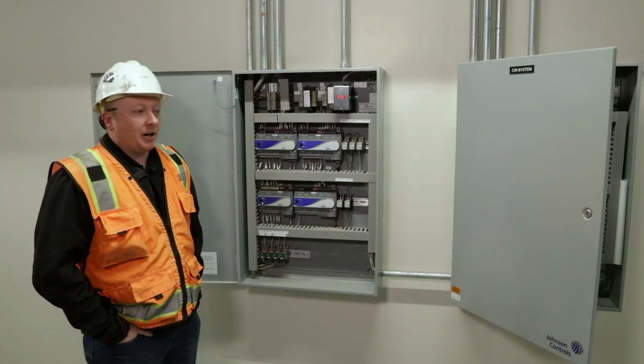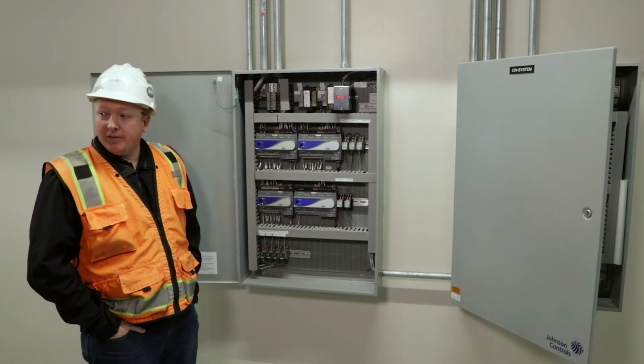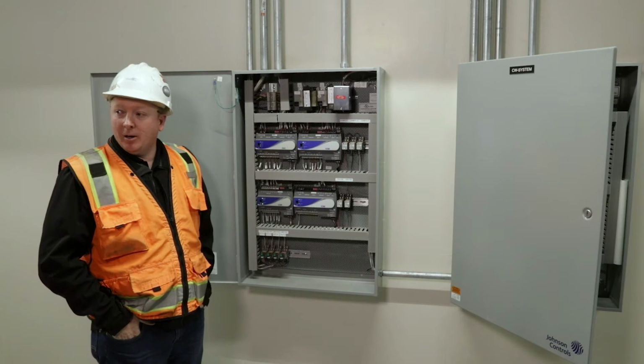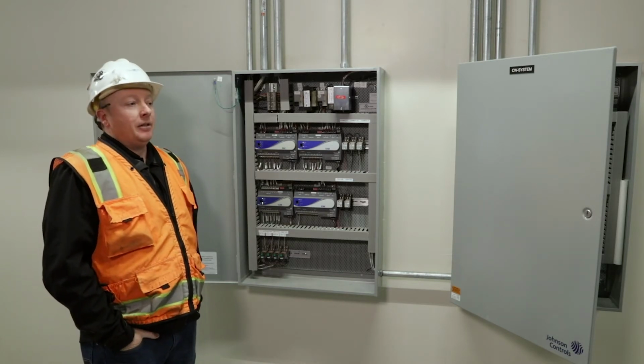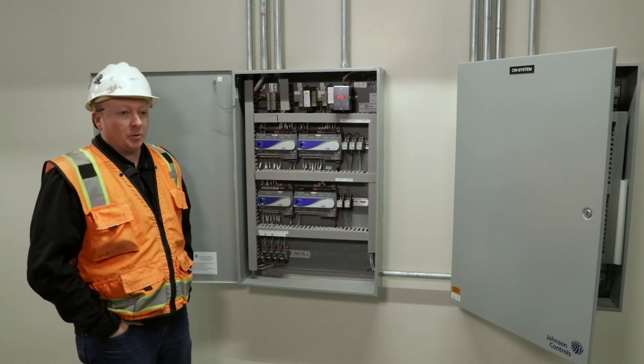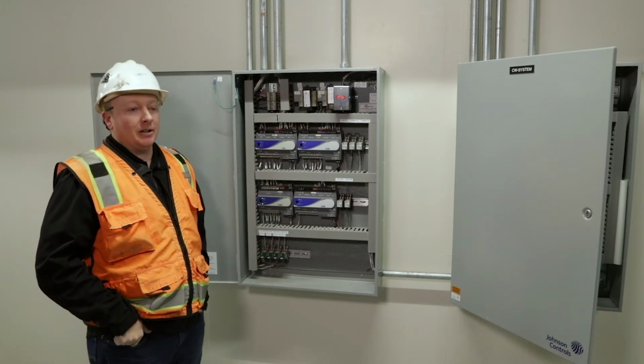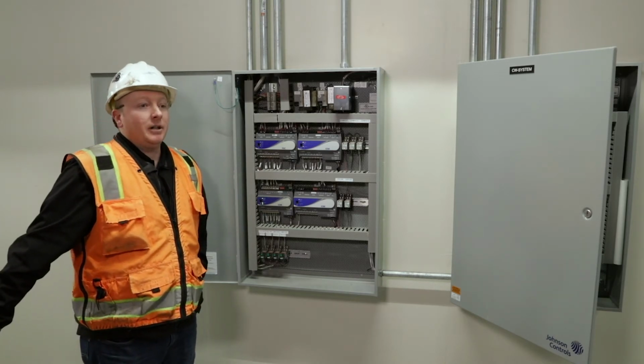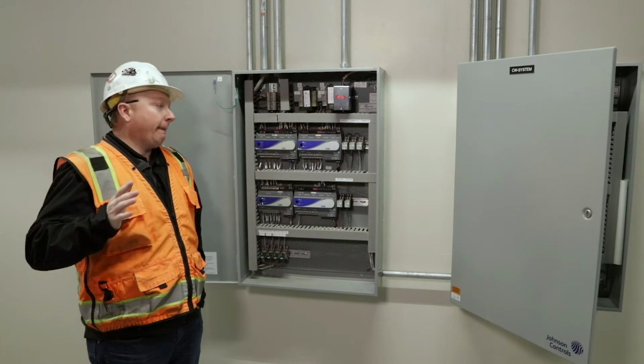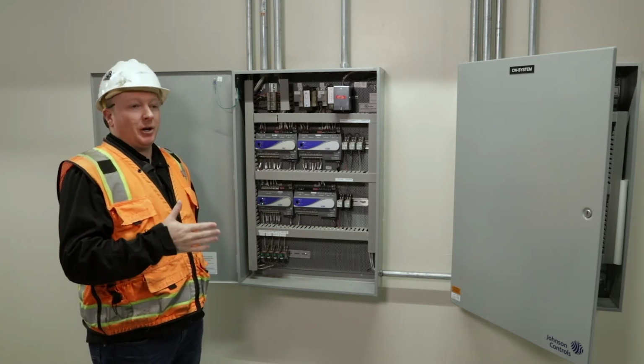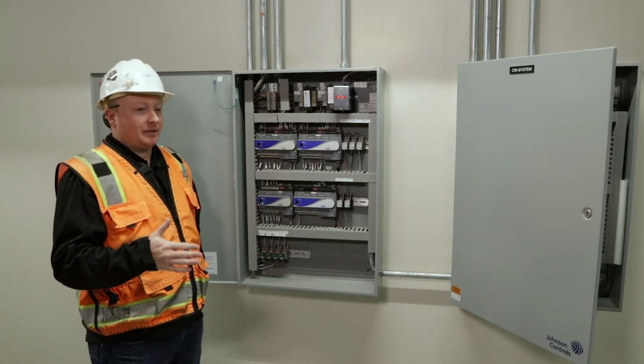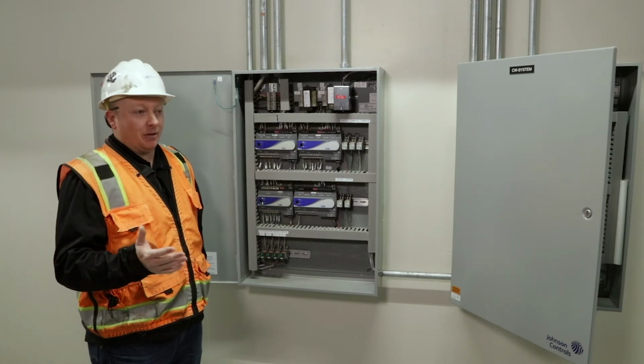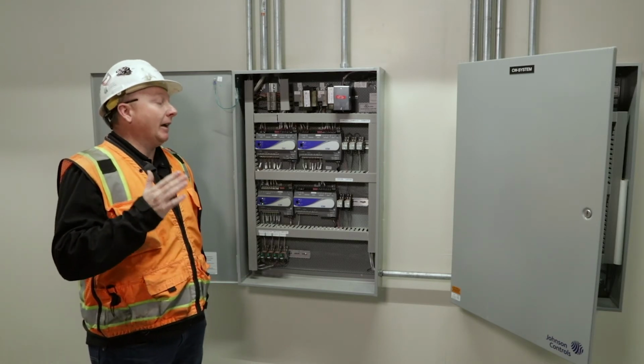Yep. So the secondary pumps are chill water pumps 4 and 5. 1, 2, and 3 are your primaries. 4 and 5 are your secondaries. Those control for differential pressure. That sensor is down at air handler 4, mounted on the air handler, and those pumps will try to maintain whatever that set point is. I don't know off the top of my head because we've been messing around with it with the balancer, but they will try to maintain.